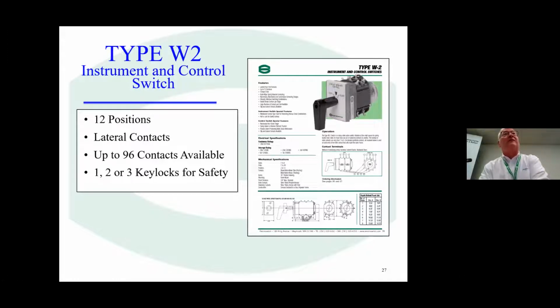Well, we bought the product rights and the design rights from Westinghouse for this and the Lockout Relay design switch. So we can now provide that legacy device for you in any applications where you need direct replacements, where you don't want to disturb any wiring, and use this heavy duty control switch, which gives you 12 positions. It's a lateral contact. It's not a rotary contact switch, but it gives you up to 96 contacts and can give you different key lock features. And if anybody has interest in that, they can contact me.